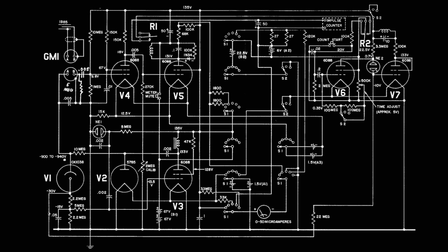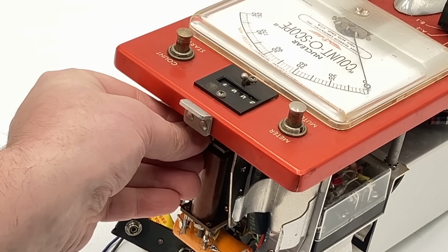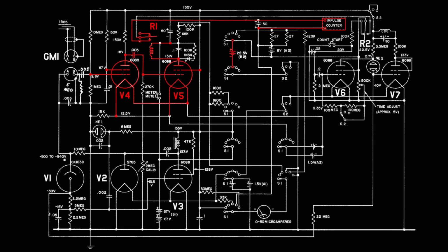When the GM tube detects a particle, the resulting pulse is sent to V4, another 6088 pentode, which amplifies it and sends it to V5, which on receiving each amplified pulse sends power from the 22.5 volt battery to relay R1, which increments the mechanical scaler. Now, the average pulse rate is also displayed by the dial, aka the linear rate meter, which is a 0 to 50 microampere ammeter powered by the 135 volt B1 battery. Ordinarily, both sides of the ammeter are held at the same 135 volt potential.